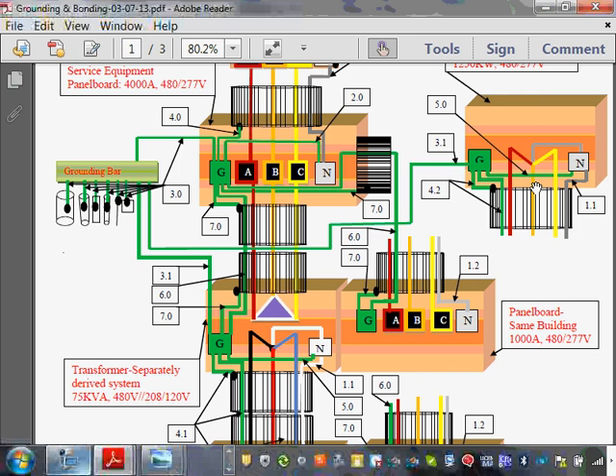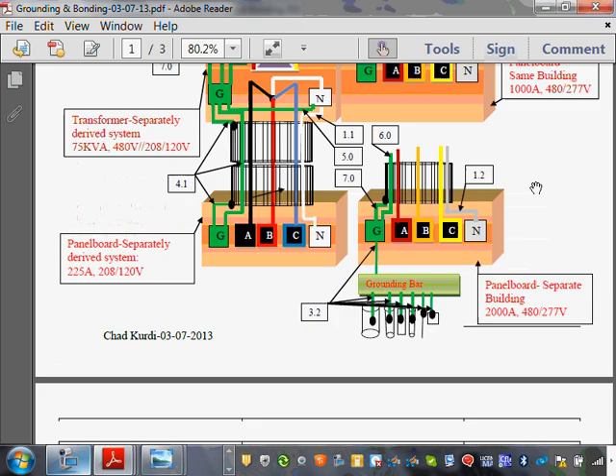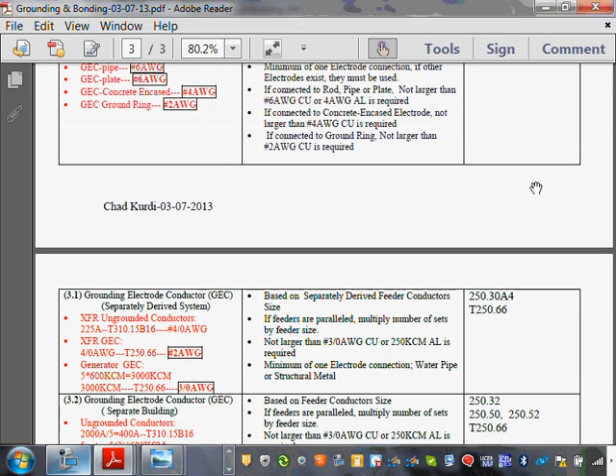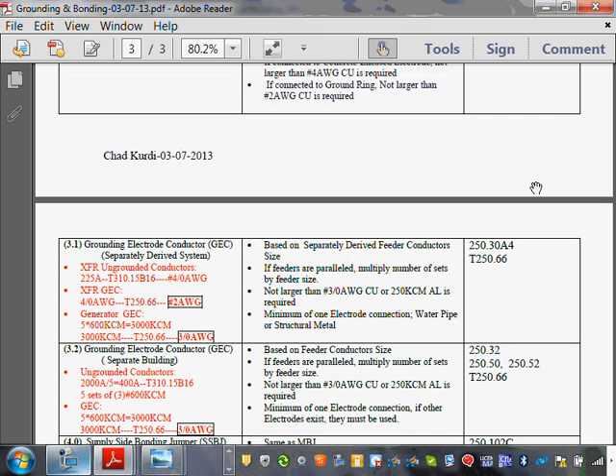Now we size the grounding electrode conductor here, either to a ground rod next to the transformer or back to the grounding electrode system. So 250.66, guys, let's go to it for the generator. Did we do that? Here's my generator. Same thing, 5 sets, gives you 3,000 to 250.66. Do not go larger than 3/0 AWG. No matter what, you do not need to go larger than 3/0 AWG.